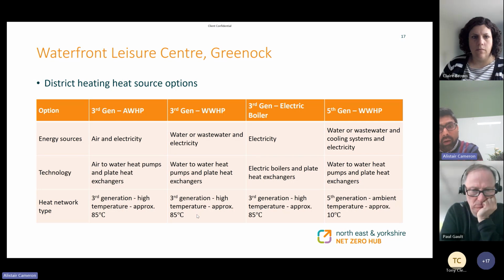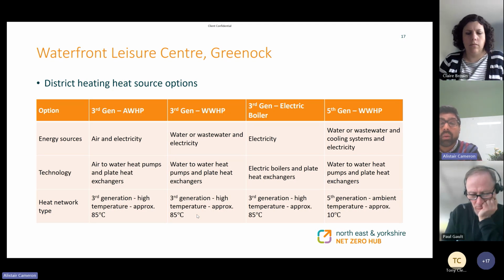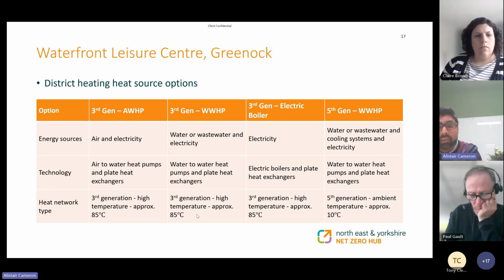Option 4 was an interesting one. This is using what we classify as 5th generation district heating, and that's essentially creating an ambient loop. So that's low grade energy serving each building, and then we upgrade that energy local to the building. So essentially, with 5th generation district heating, we're potentially just taking water from the Clyde at 10 degrees, and that water is fairly stable throughout the year, and that energy at 10 degrees is then upgraded locally via water to water heat pumps at each building, and that gives the buildings the opportunity to provide a heating medium that suits the building and its performance requirements.